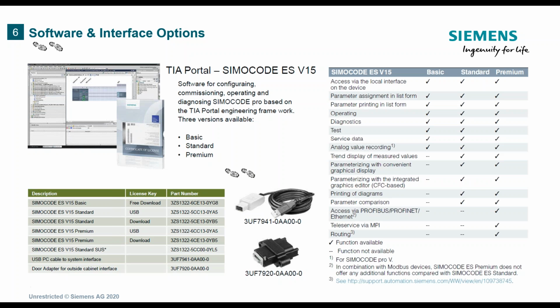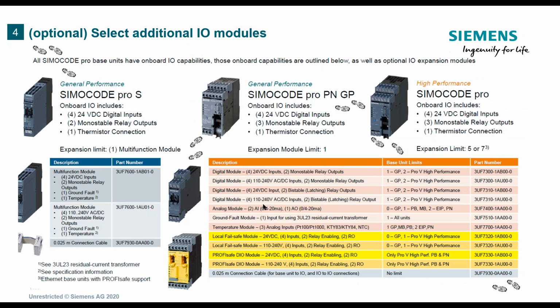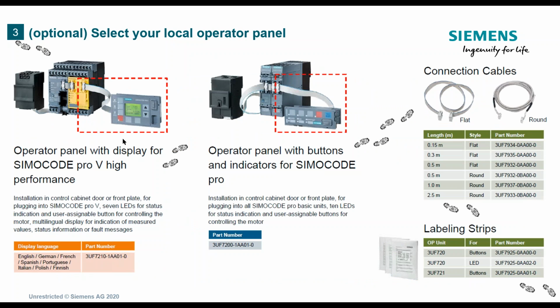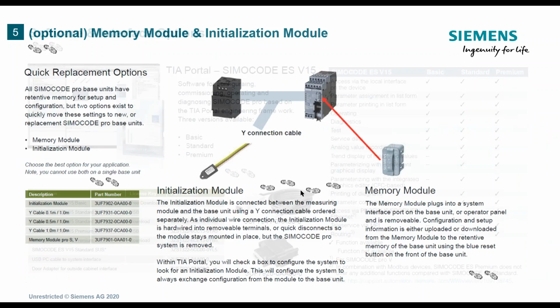And I said, "Well, do you need the operator panels?" And he said, "No, it's more of a want than a need." I said, "Okay. But how about if we don't get rid of all of it? We still give you the functionality of the operator panel." And I'm speaking of this operator panel here. He had one on every MCC door. What he decided to do, what he and I talked about, is that I was going to put this little bulkhead fitting in the door of every MCC bucket. And then he purchased one operator panel, put that in a little NEMA 1 box and brought the cable out.